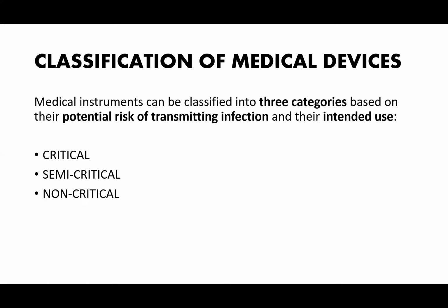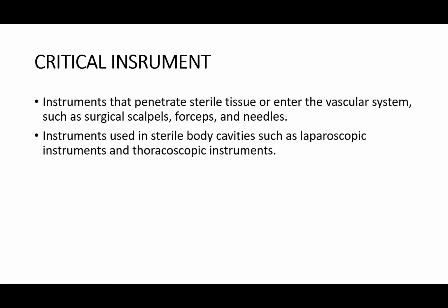Now, how do we classify medical devices? Medical instruments can be classified into three categories based on their potential risk of transmitting infection and their intended use. They could be classified as critical instruments, semi-critical instruments, or non-critical instruments. Critical instruments are those that come in contact with sterile surfaces or sterile cavities. Semi-critical instruments contact non-sterile cavities, while non-critical ones are those that come in contact with intact skin and mucous membrane.